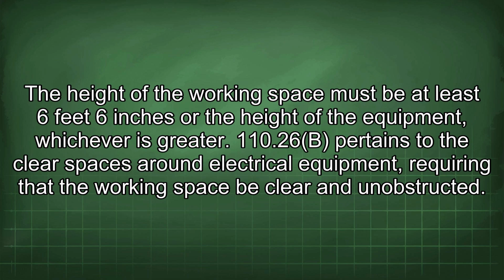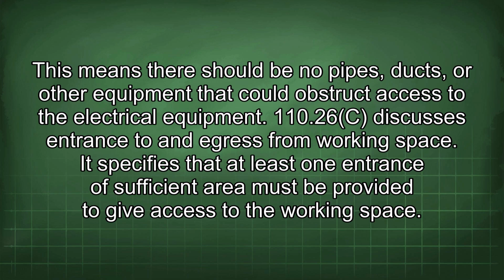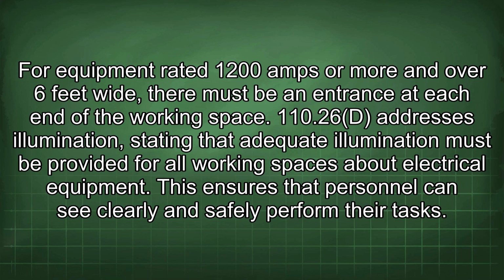110.26b pertains to the clear spaces around electrical equipment, requiring that the working space be clear and unobstructed. This means there should be no pipes, ducts, or other equipment that could obstruct access to the electrical equipment. 110.26c discusses entrance to and egress from working space. It specifies that at least one entrance of sufficient area must be provided to give access to the working space. For equipment rated 1200 amps or more and over 6 feet wide, there must be an entrance at each end of the working space.